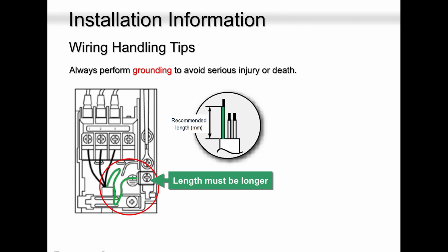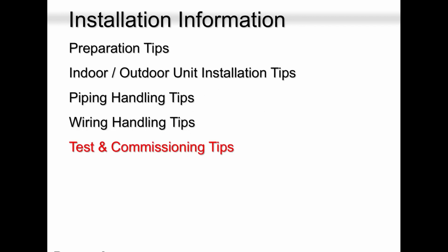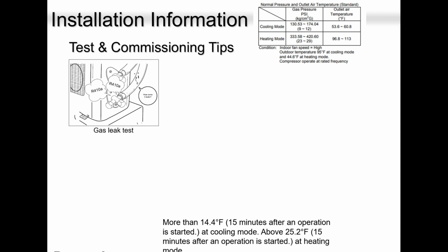Wiring. Always ground your wire. Don't just run wires and forget about the ground. Ground is very critical, very crucial if you are doing the wiring, okay? Always pressure test the system. Please don't over pressurize the system, guys. 350 to 400 psi is more than enough for your nitrogen test.